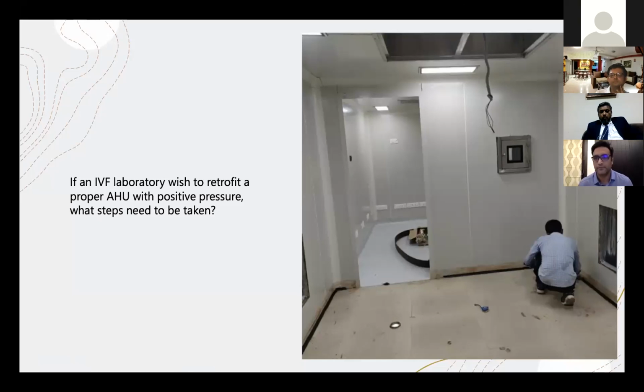Yes, sir, thanks. This is a very important point. When we talk about any clean area, positive pressure is very important. While maintaining it, we don't want to disturb other parameters like temperature, humidity, and pollutant level. Typically, standalone units suck air from the room, cool or clean it, and throw it back, so they cannot provide positive pressure.